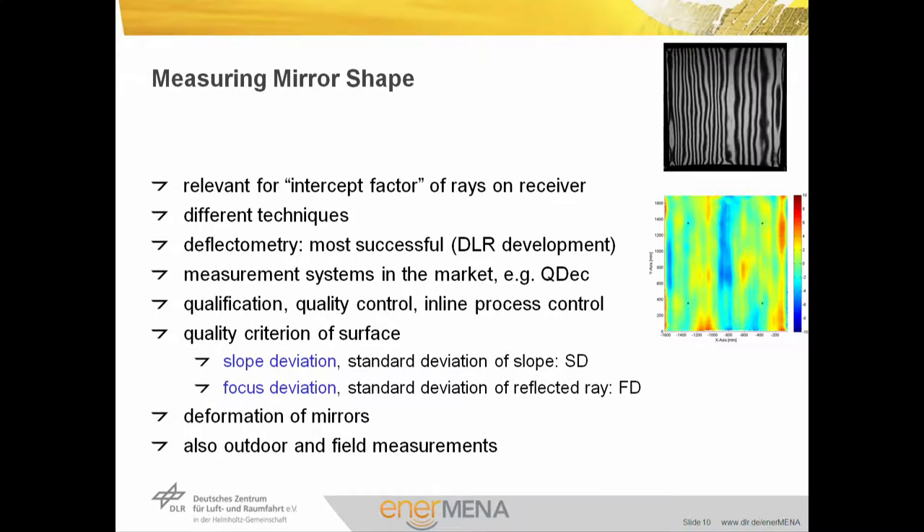Mirror shape is relevant for the intercept factor of the rays on the receiver. We have different techniques to measure the shape. Deflectometry is the most successful one, developed at DLR over the last years. We already have measurement systems in the market — for example, the QDec system — which produces the kinds of pictures shown on this slide. Such measurements are used for the qualification of products and prototypes, in quality control in production, and also in in-line process control in manufacturing. The quality criterion of the mirror surface is the slope deviation — the standard deviation of slope values, SD — or the focus deviation, FD, the standard deviation of the reflected ray. It gives us a quality parameter for the form or deformation of mirrors.